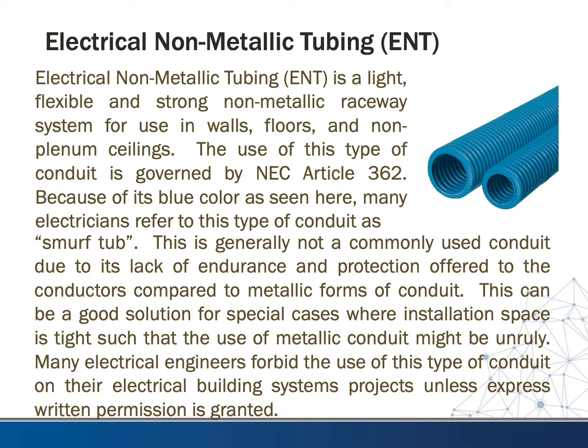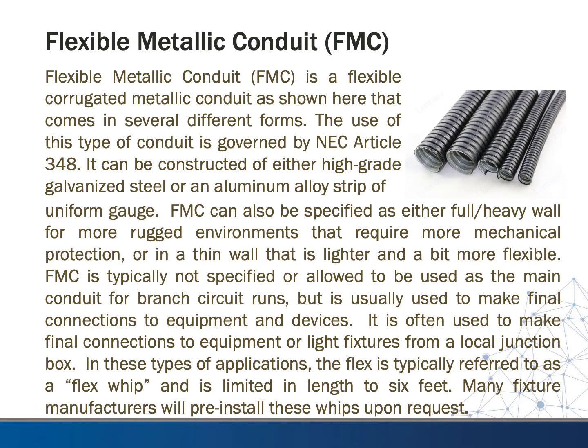The first type is electrical non-metallic tubing, or ENT. This is a light, flexible, and strong non-metallic raceway system for use in walls, floors, and non-plenum ceilings. Its use is governed by NEC Article 362. Because of its blue color, many electricians refer to this as 'smurf tube' — the common field slang. ENT is generally not a commonly used conduit due to its lack of endurance and protection compared to metallic conduit. It can be a good solution for tight installation spaces where metallic conduit might be unruly, but many electrical engineers forbid its use on building system projects unless express written permission is granted.